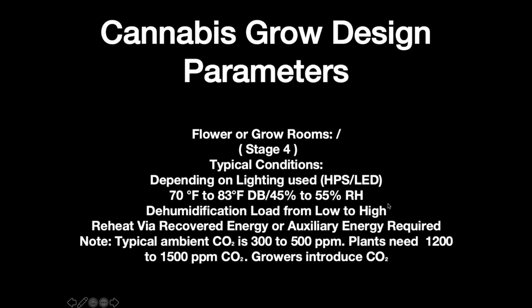Because we're doing such a heavy dehumidification load, we're doing a lot of reheat. And you've either got to reheat via recovered energy, which is hot gas reheat, or you've got to supply auxiliary heat of gas or hot water coils, etc.